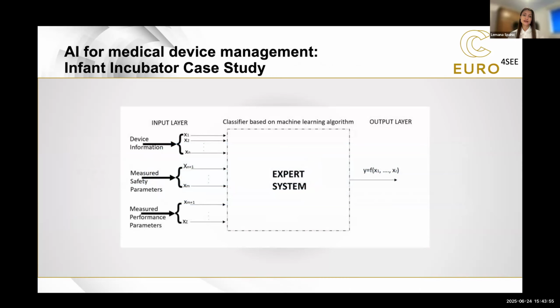When it comes to the safety parameters, it stems from visual inspection and electrical safety inspection. So whether the device chassis is complete, whether all the cables are there, whether original parts are present on the device, whether there are clear labelings and markings on the device, whether it passes the electrical safety inspection. And then if it passes all of those, it goes to performance assessment. Now, for performance assessment, we have different echelons that we use for different medical devices, and we measure the parameters that are specific for that device. For example, for the infant incubators, it's the humidity and temperature that we always measure, because those two are the fundamentals of a functional infant incubator.